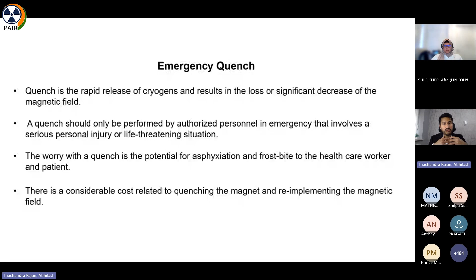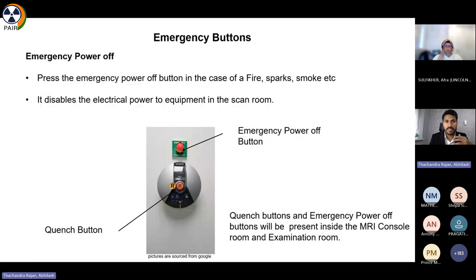It doesn't quench the magnet, but this can be used in case of fire, sparks, or smoke happening in the magnet area. So we can cut down the power to the magnet room, and then we can allow the firefighters or anyone to enter after screening and taking extra precautions. The quench button can be pressed by an authorized person, but in order to bring this switch back, we have to call the engineers. We have to keep the control access area safe.